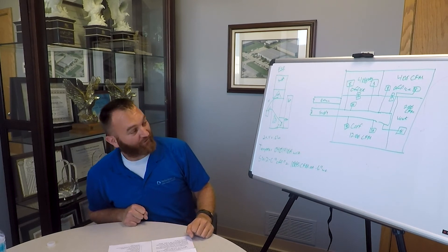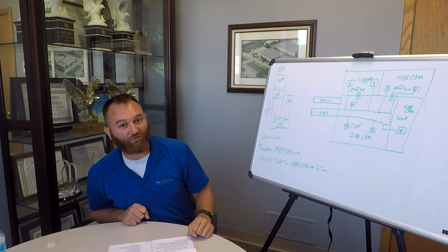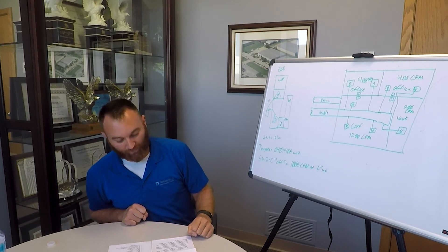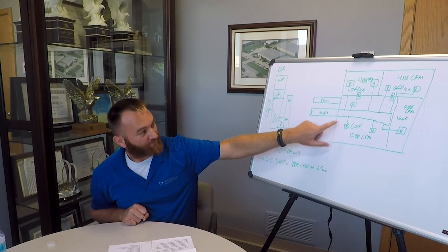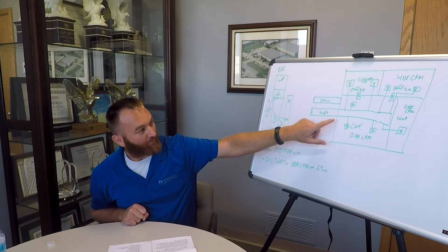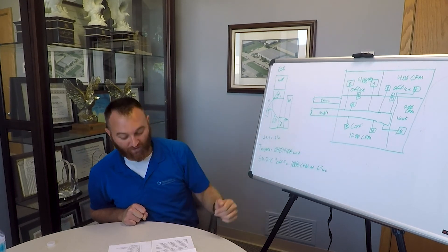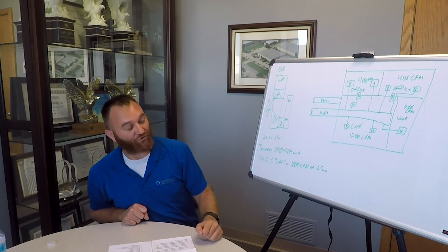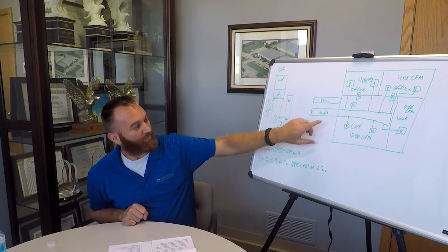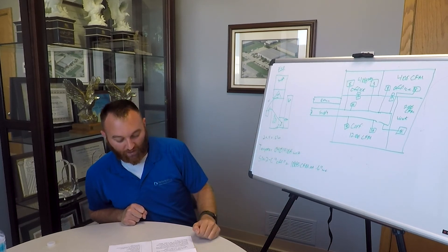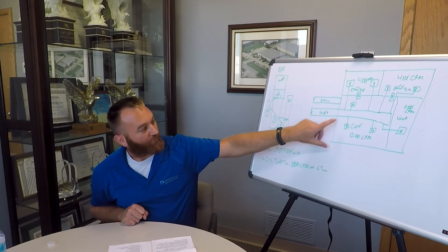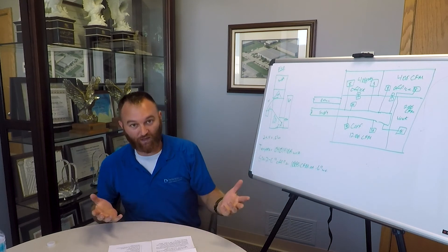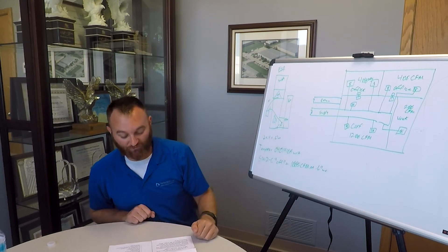Air balancing should always be performed by a qualified person with calibrated tools. This can include a balance hood for each supply or return vent, or a magnehelic or digital manometer with the pitot-static tube. You use these tools to adjust your branch dampers to provide the proper CFM.